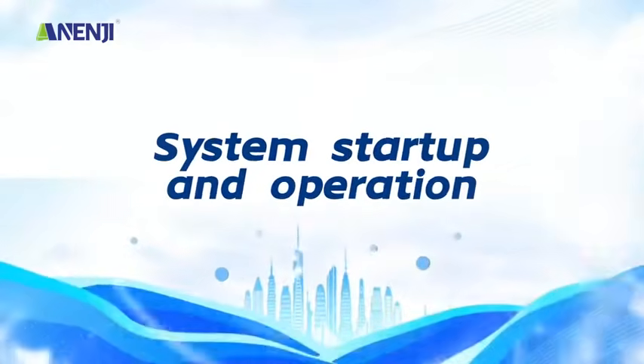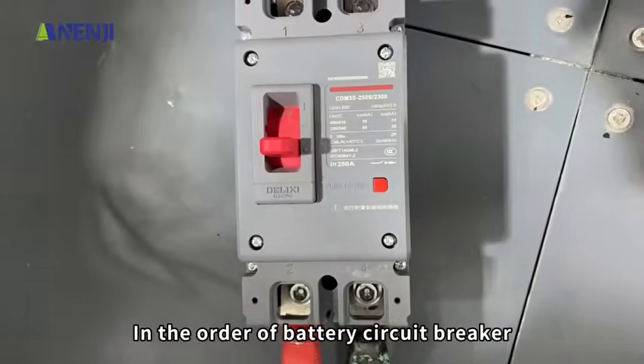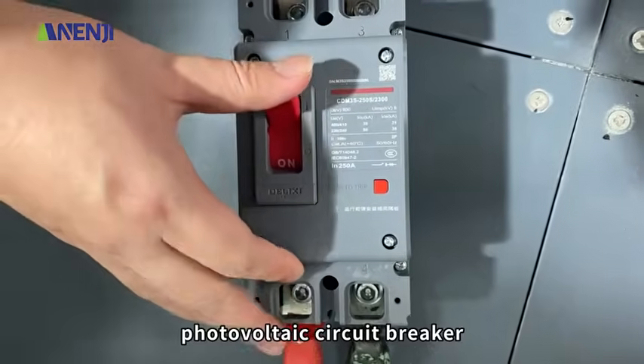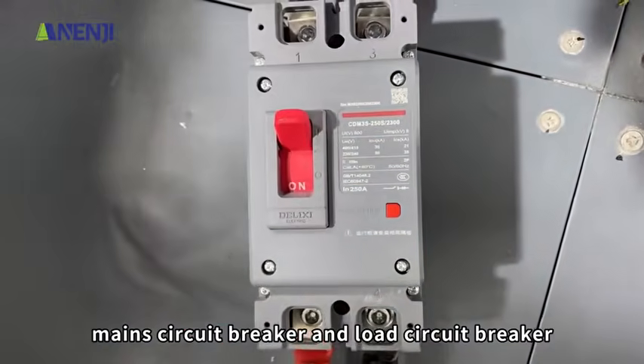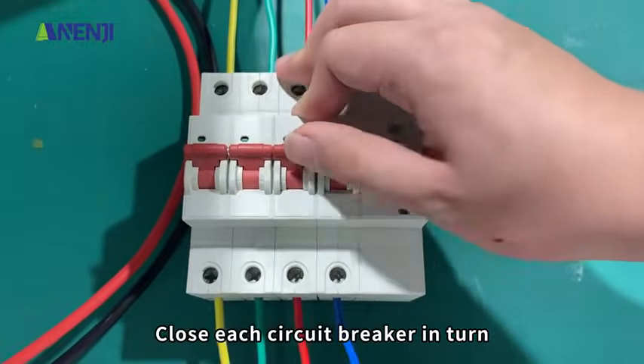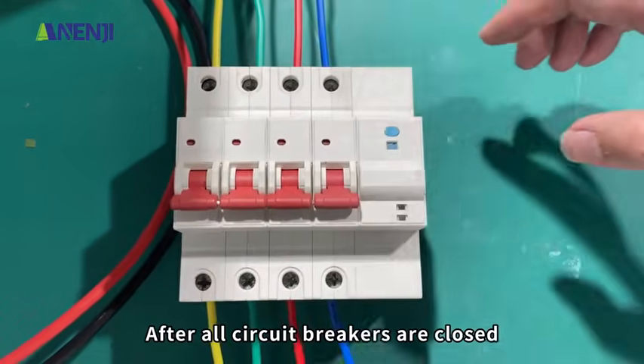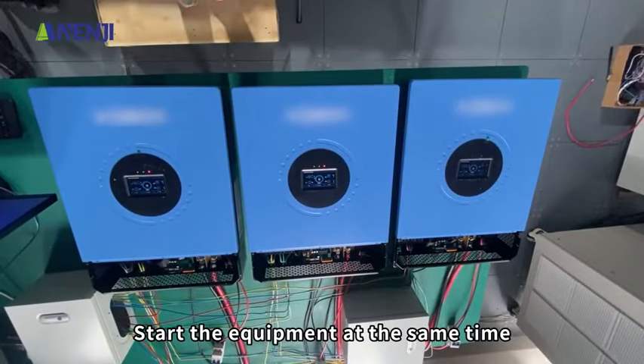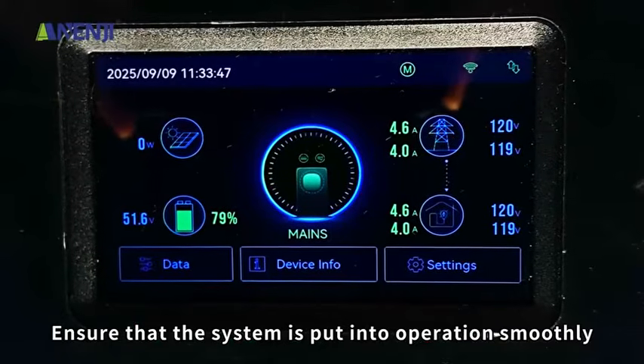System startup and operation. In the order of battery circuit breaker, photovoltaic circuit breaker, mains circuit breaker, and load circuit breaker. Close each circuit breaker in turn. After all circuit breakers are closed, start the equipment at the same time. Ensure that the system is put into operation smoothly.